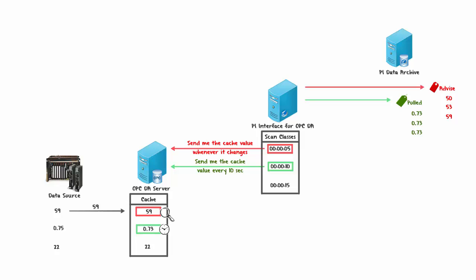Finally, within the next 10 seconds, if there is an update on the Data Source, it updates the Cache, and the next time the PI Interface for OPC DA sends a request to the OPC Server, it gets the new value. You can see there's a lot of traffic between the PI Interface and the OPC DA Server, and a lot of repetitive values in the PI Data Archive. In most scenarios, Advise Points are much better to use than Polled Points — only use Polled Points if you absolutely need a value at every scan frequency.